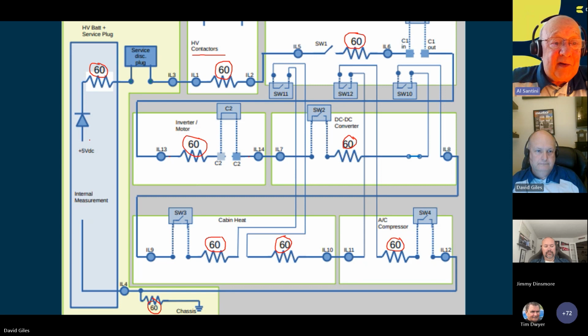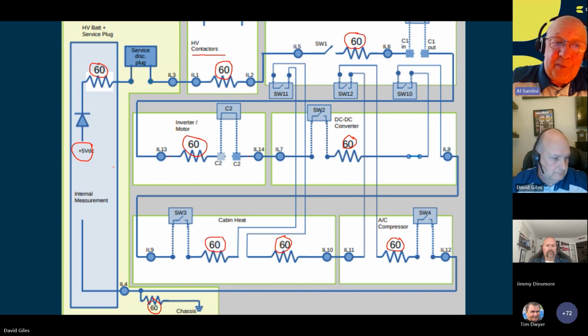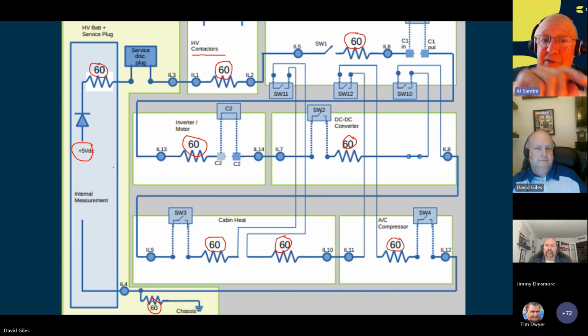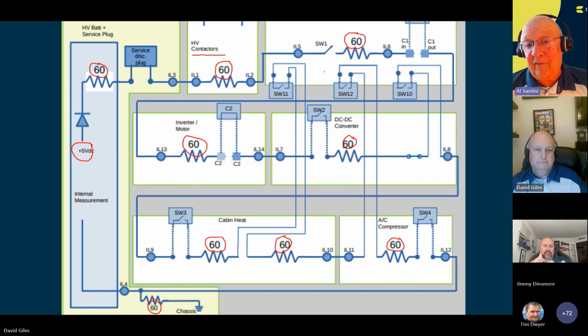Notice all the way on the left-hand side where it says 5 volt DC - this circuit is being powered by 5 volts. So if you put 5 volts as a pressure to a circuit with six, seven, eight, nine 60 ohm resistors, you're getting almost no current at all. But the point is you are getting current. When that current gets back, it's measured internally, and that says there's a complete circuit out there. Without the complete circuit, the system is dead. Everything has to be correct before this system becomes lethal, or the contactors close and we actually begin to run high voltage.